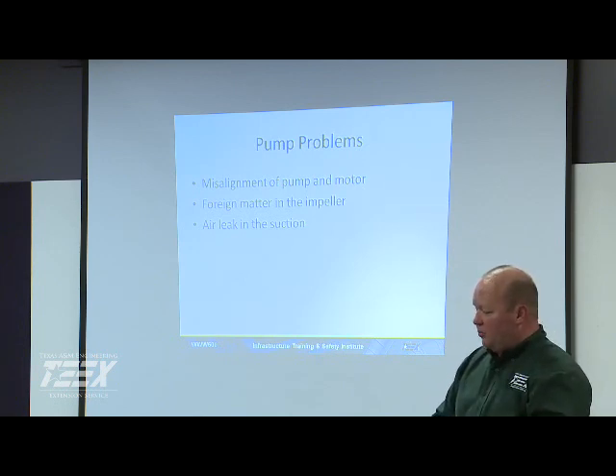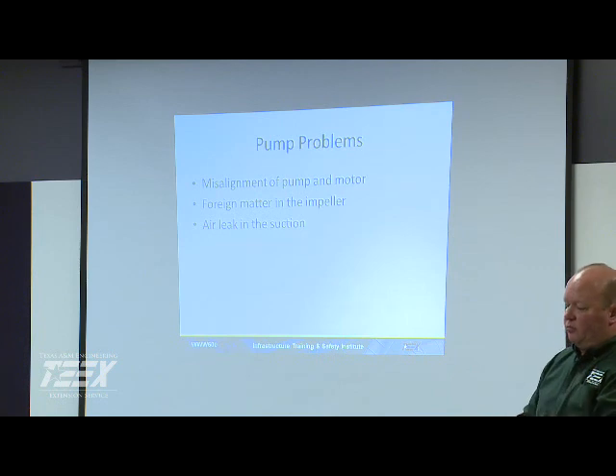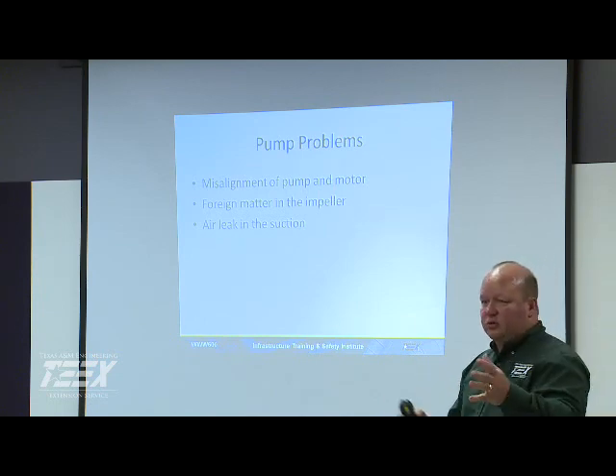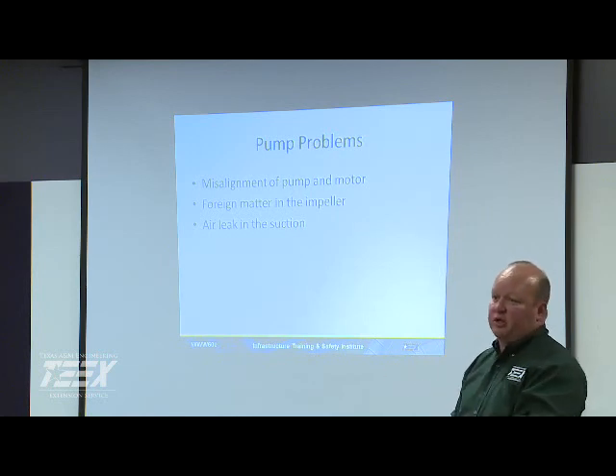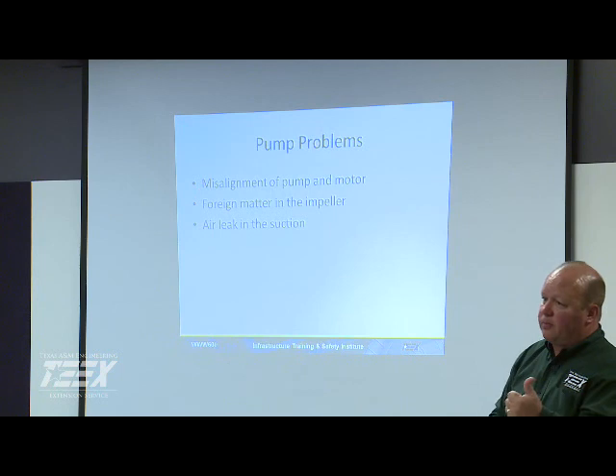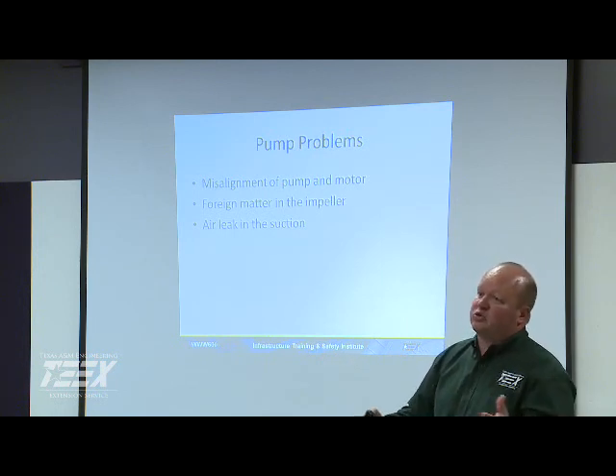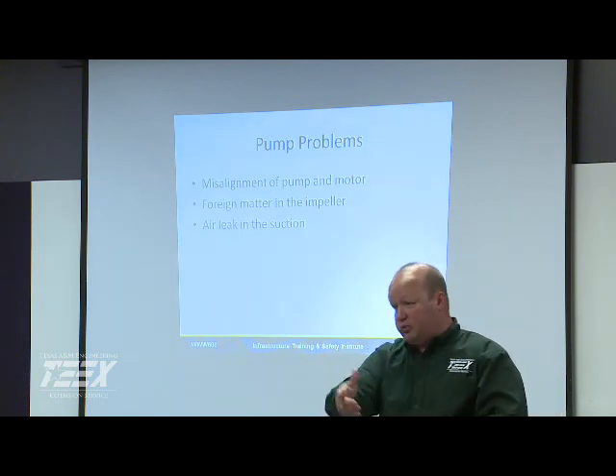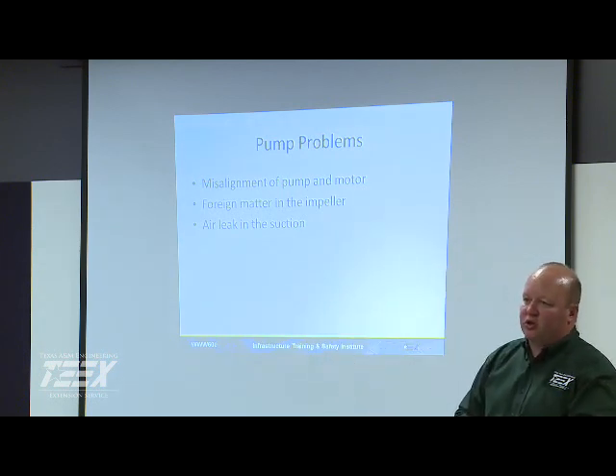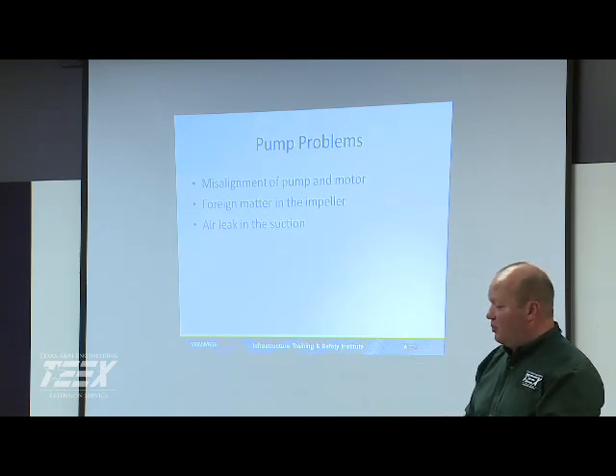Yeah, one of the things that I promote a lot, even on a basic O&M program, is you can go to the auto parts store and buy an infrared thermal temperature detector. They're not that expensive, $100 or so. If you make it a regular part of your program, you can look at your bearings and at your leads coming in on your switchgear, and you can determine when you have hot spots. If you have a hot spot, you need to go and take care of it. You've got a bearing that's burning up, or a lead that's going bad. If you do that ahead of time, you can prevent a lot of catastrophic failure. We even had switchgear fires that burned up a lot of stuff because we had lead issues coming in. So those are easy ways. If you can't afford ultrasound vibration analysis, which is your high-end predictive maintenance, something simple can really go a long way to helping your plant.